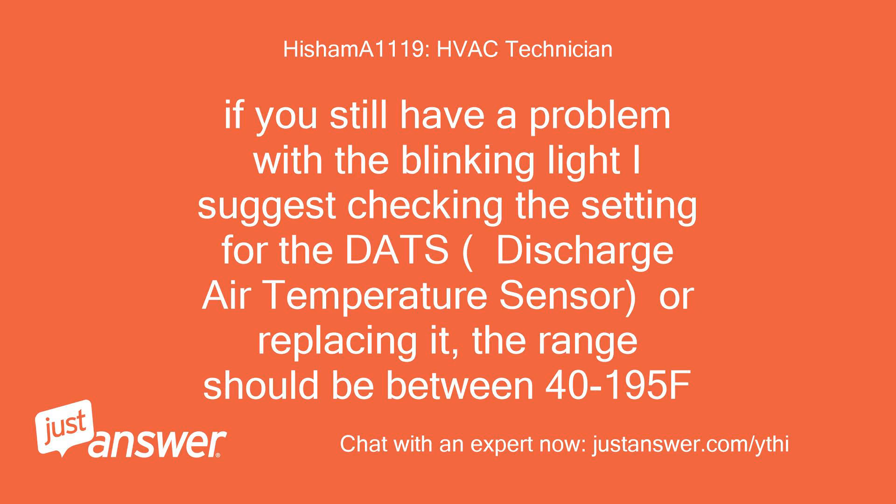If you still have a problem with the blinking light, I suggest checking the setting for the DATS — Discharge Air Temperature Sensor — or replacing it. The range should be between 40 and 195°F.